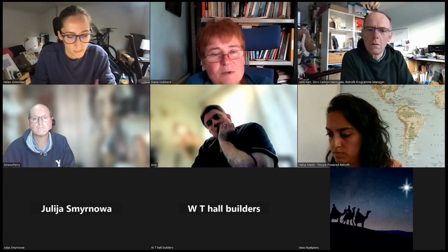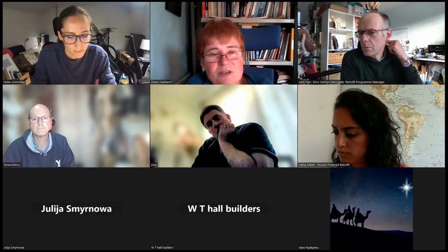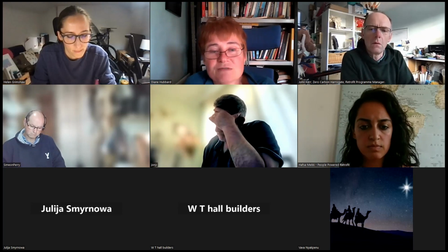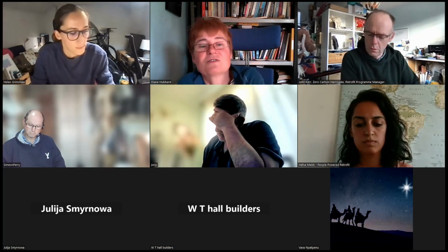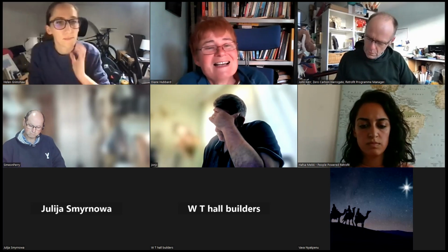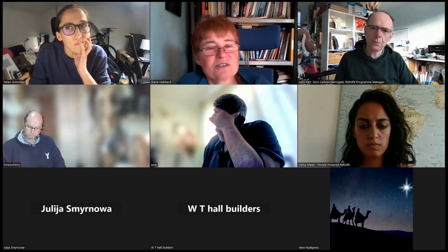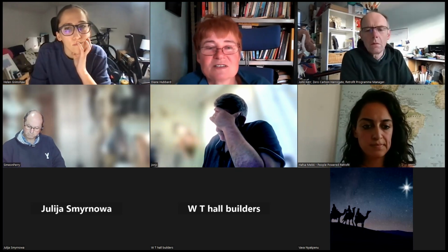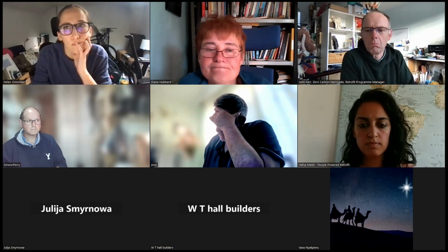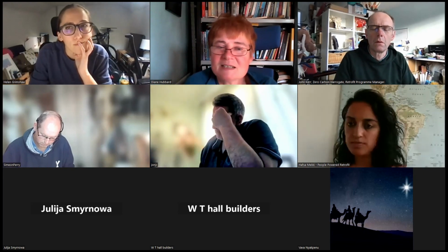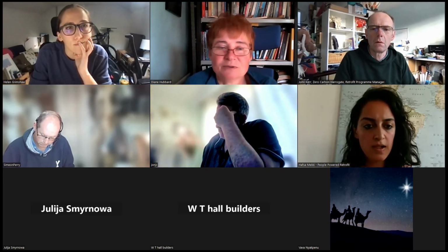When I'm doing surveys, I use a camera that's 240 by 320 pixels, and that's a good resolution for buildings. That should give you everything that you're looking for really. So it doesn't work as an app. The apps are a bit smoke and mirrors-ish. It's got to be a specific device. Does that answer the question? But 500 quid will get you something that will give you a basic useful level.